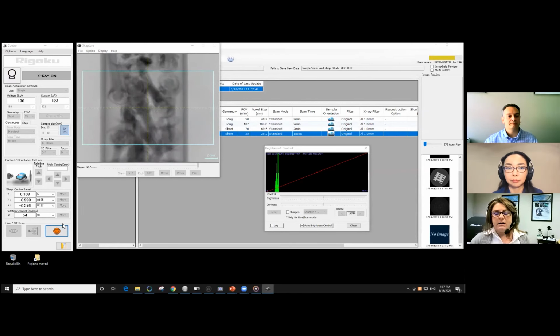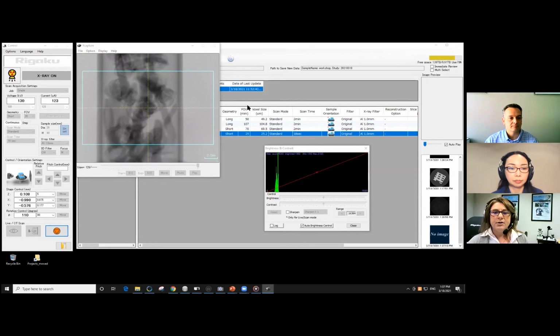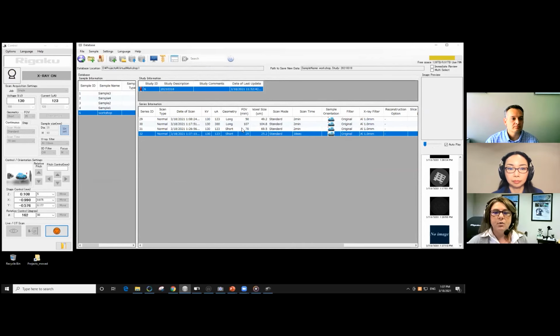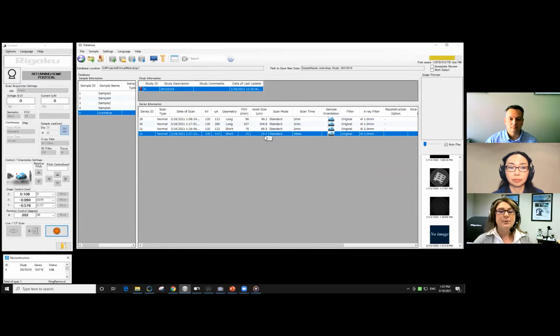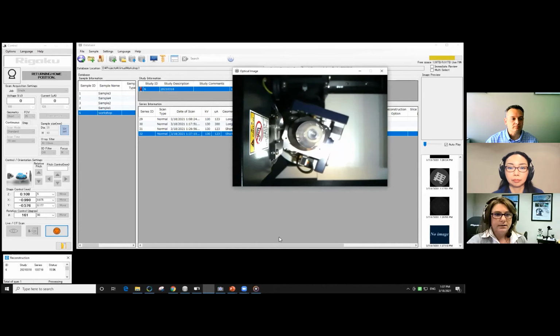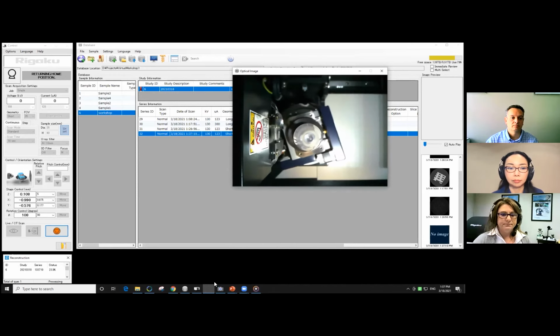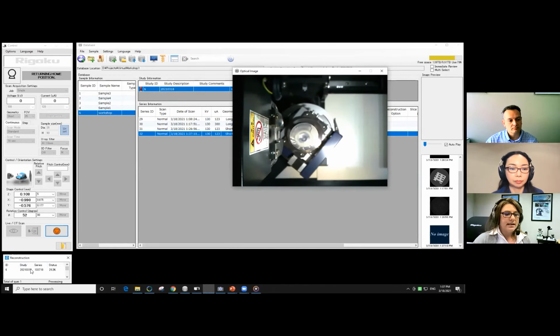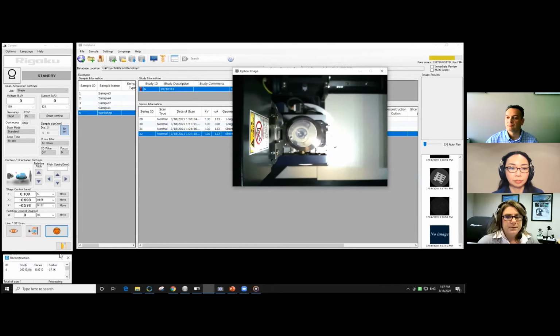One of the things that I'll just mention, if you can see right behind here, you'll see the last 2 scans that were collected for the 70 millimeter field of view and the 25. But as a consequence of choosing the smaller field of view, our voxel size, or the 3-dimensional size for which we sample our images, is now smaller. And by virtue of that, that's where we're going to get the gain in resolution. So it's just returning it back to 0. And in the bottom right here, we can see our reconstruction running right there.